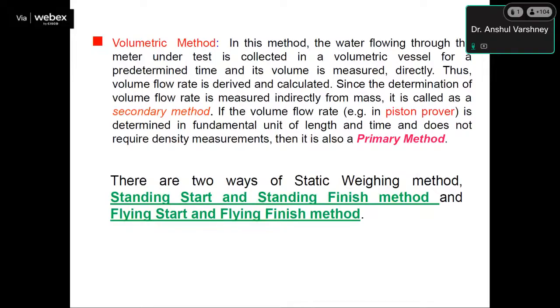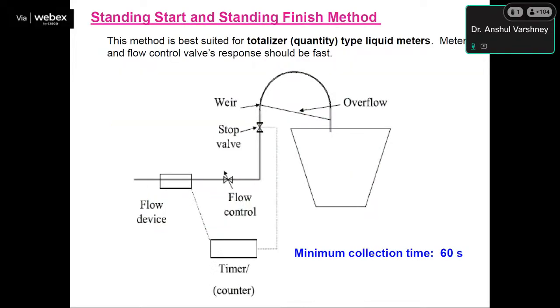There are two ways of static weighing: standing start and standing finish, and flying start and flying finish. This is the standing start and standing finish method. This method is best suited for totalized type liquid meters and flow. However, in this type of method, the meter and flow control valve response should be as fast as possible. The minimum collection time for the standing start and standing finish method is 60 seconds.